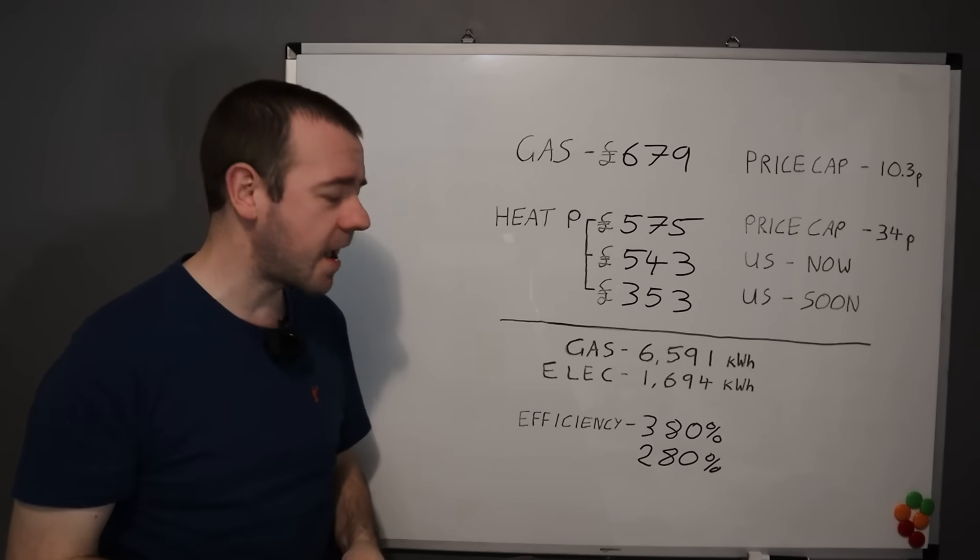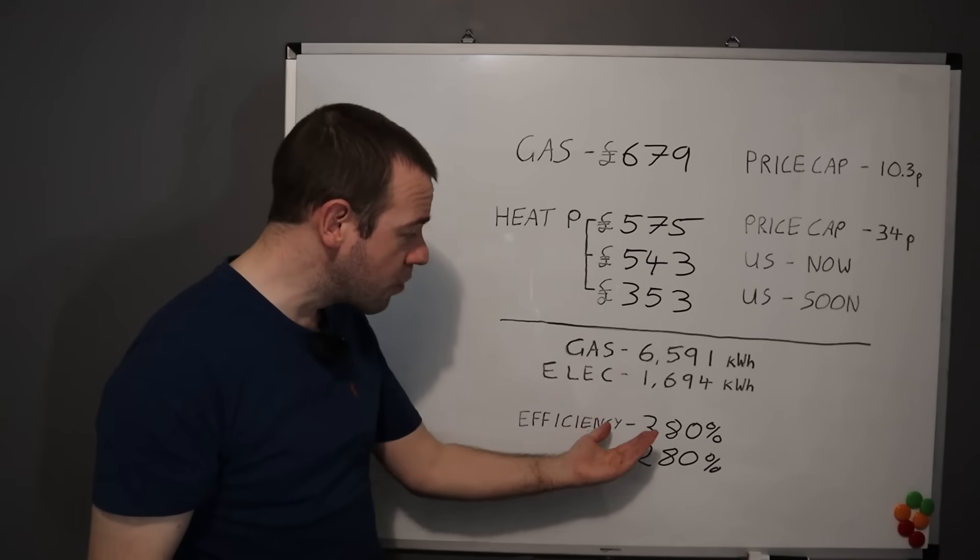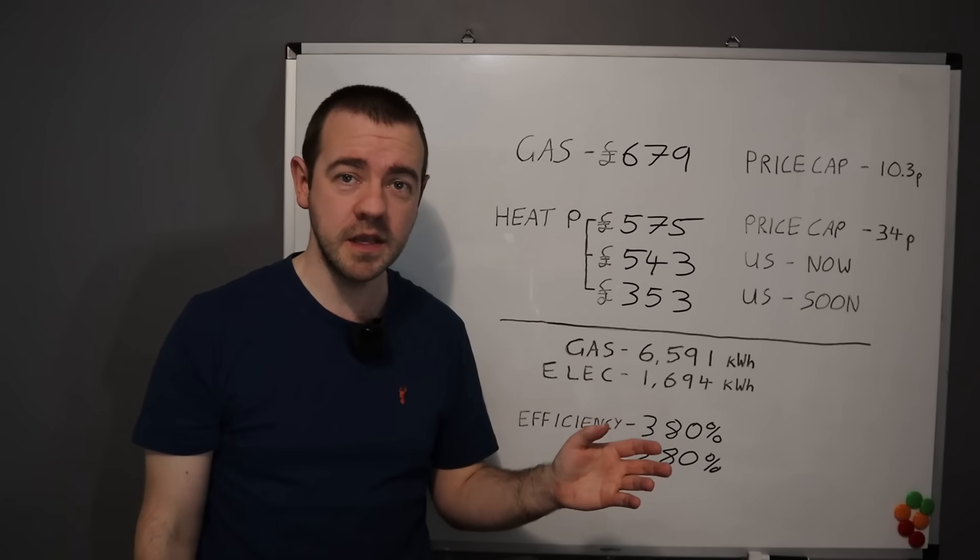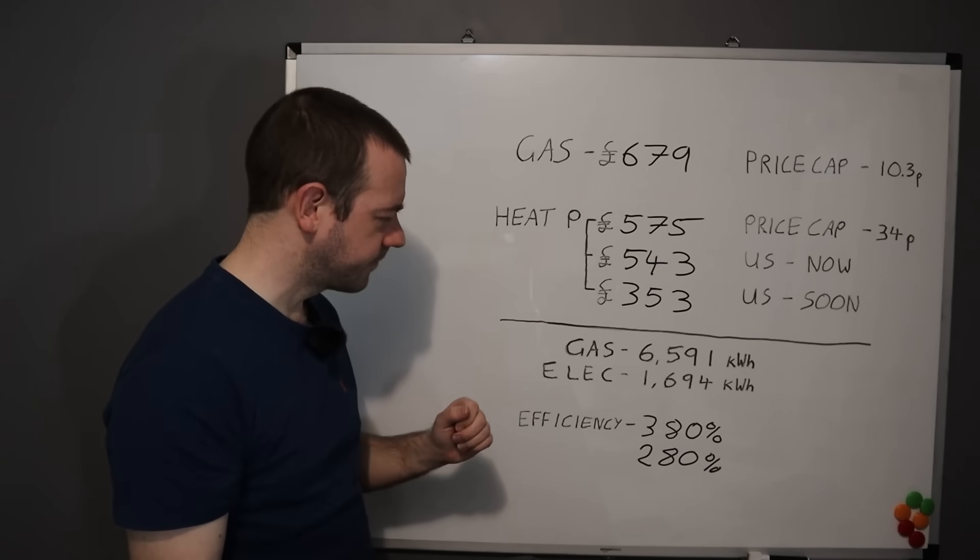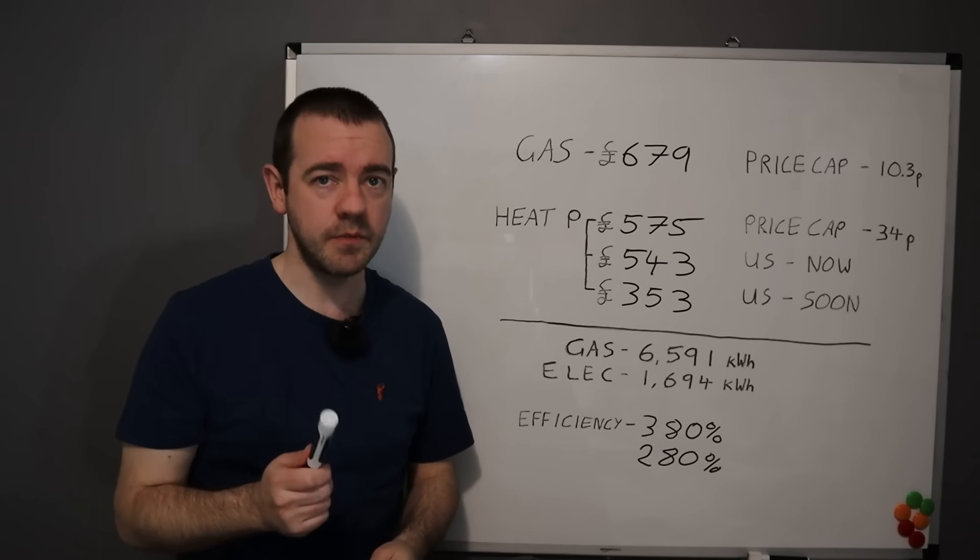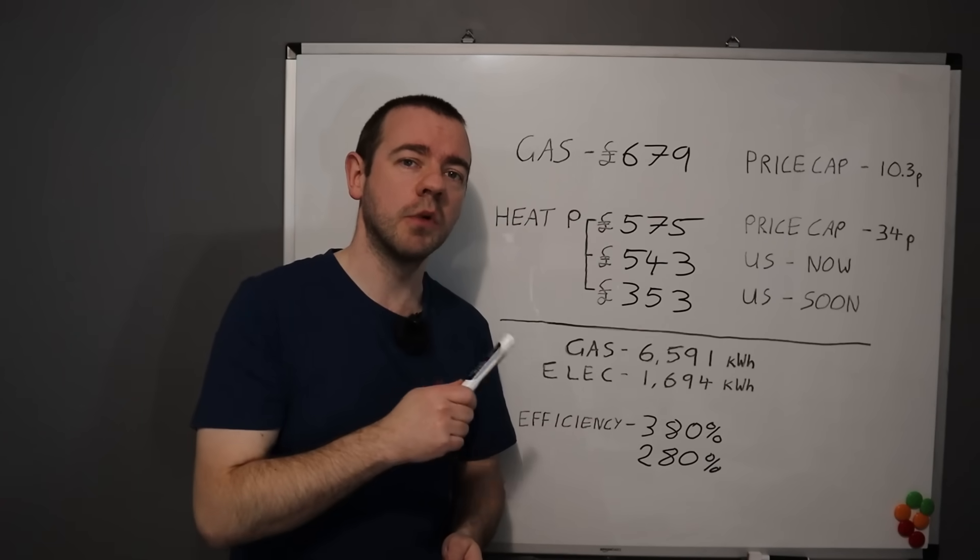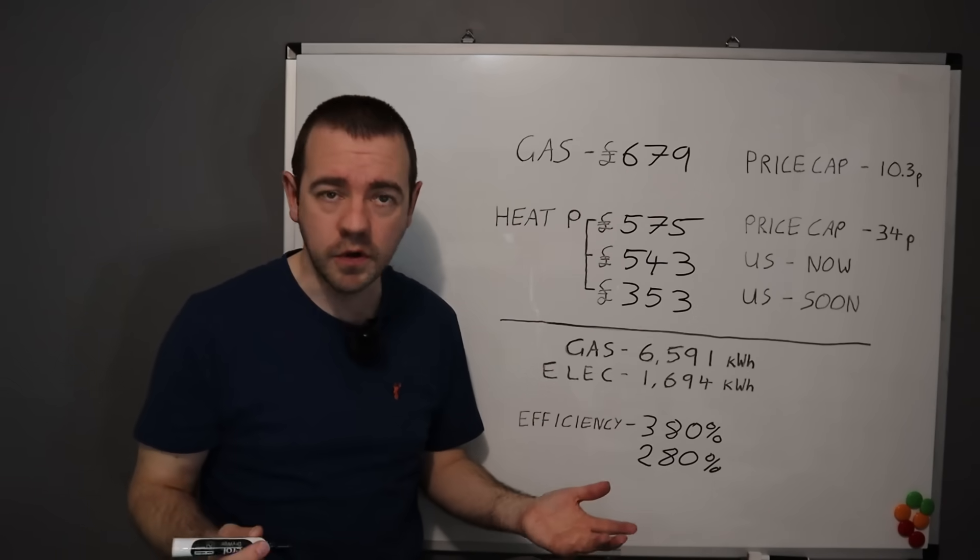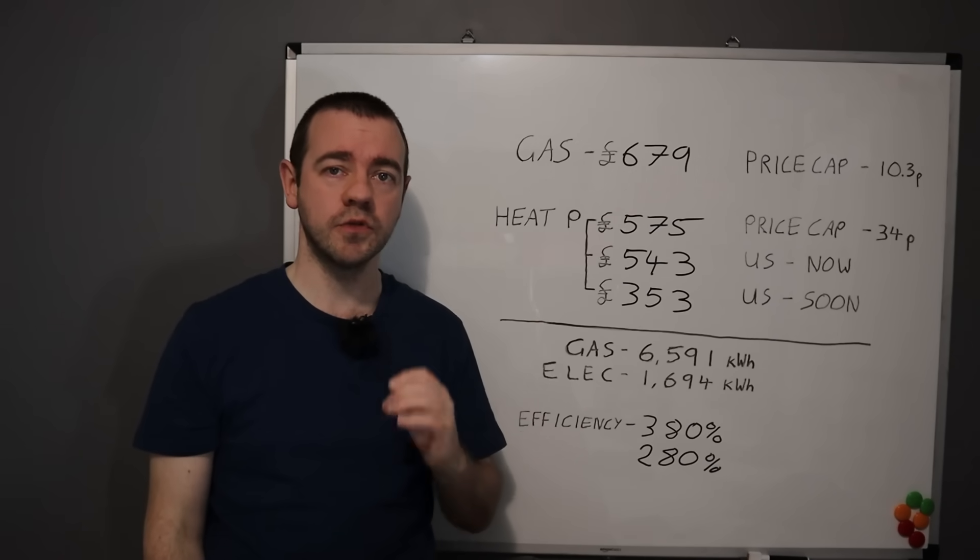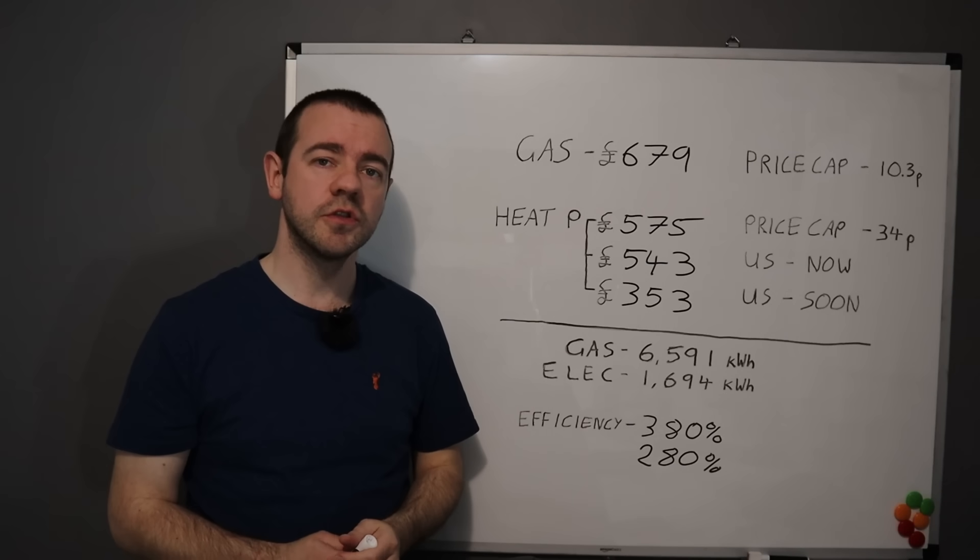Now the efficiency, there's two ratings for this. One is the efficiency of the heating system that's set to a flow temperature of 40 degrees. And the other one is an efficiency rating for the hot water because that's set at a temperature of I think 51 degrees centigrade. So that's why you've got two different efficiency figures. So this is the, remember, the total efficiency since the middle of September to the end of February. So again, worst case scenario, and we have an efficiency of 3.8 or as I prefer to do it, 380% efficiency. So that's for the heat pump before winter just for a couple of months and then winter itself.